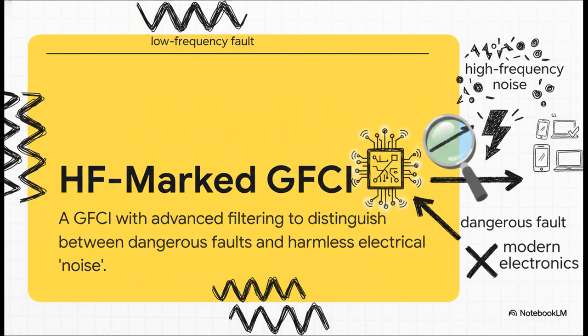So let me introduce you to the HF-marked GFCI. HF stands for high frequency. These new devices have advanced filtering technology built right in, specifically designed to tell the difference between the low-frequency signature of a real, dangerous ground fault and the high-frequency chatter coming from modern electronics.